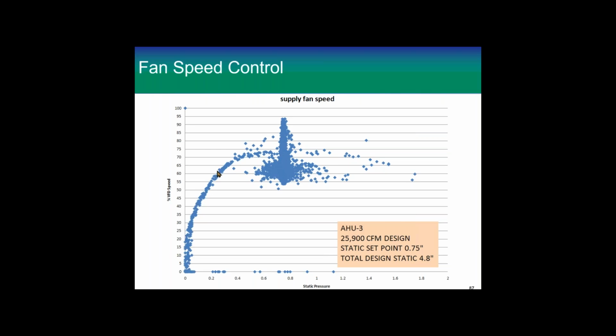Anyway, you can see the fan starts up, it runs up here, and then it hits this speed, and then it works back and forth and back and forth based on that static pressure sensor. But the problem is, it was designed, we said we're going to save energy down to 30%. This fan can run at 30% design, but because of where it was set, it will never slow down more than 53, 54%. But if you had this reset system and no damper ever opened, it would go down to the 30%. So that's why it's important to allow it to go down as low as it can, to get as much energy savings from that variable speed drive as we can.